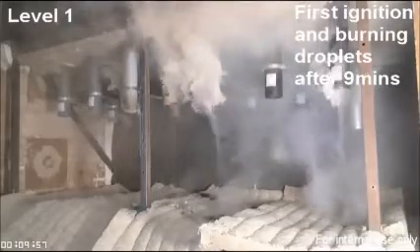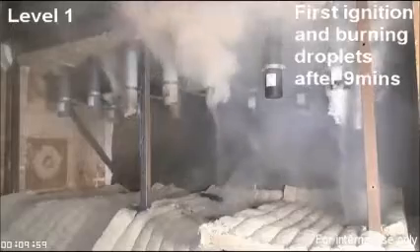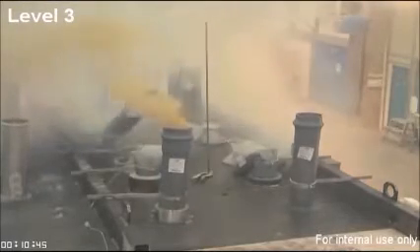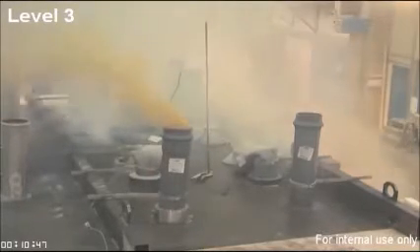After ten minutes and forty-six seconds, we see the first fire blowout from the PP pipe. The fire also penetrates the heat-activated fire seal outside the PP pipe. The smoke and the burning droplets show that, at this time, the heat-activated fire seals have not yet closed towards the lower deck. Meanwhile, on the upper deck, it seems the heat-activated fire seals are now starting to work.